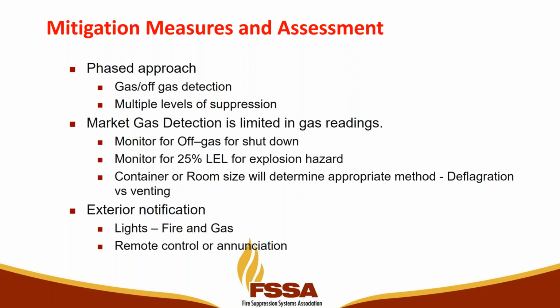You've got to deal with standard gas detection. One of the problems we run into with monitoring hydrogen is, if you've suppressed the catalytic bead's ability to monitor hydrogen, are you going to get true readings? So you might have to look at a reference gas, because hydrogen, as far as I know, can only be picked up on a catalytic bead type sensor. It can't be picked up on an IR. So it has the potential to get fouled.